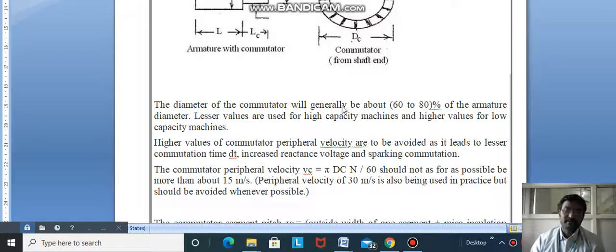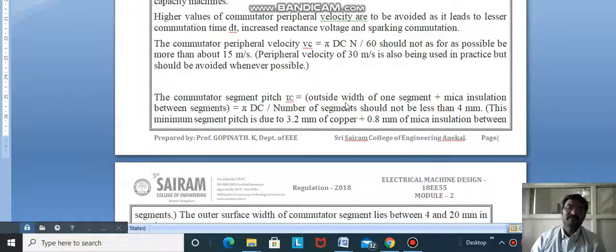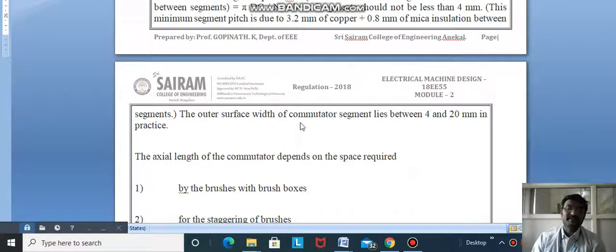The commutator segment pitch, the outer width of one segment plus mica insulation between segments, equals π Dc divided by number of segments and should not be less than 4 mm. Minimum segment pitch is 3.2 mm of copper plus 0.8 mm of mica insulation. The outer surface width lies between 4 and 20 mm in practice.